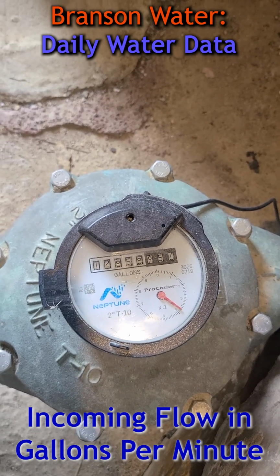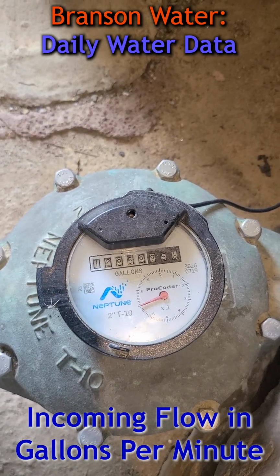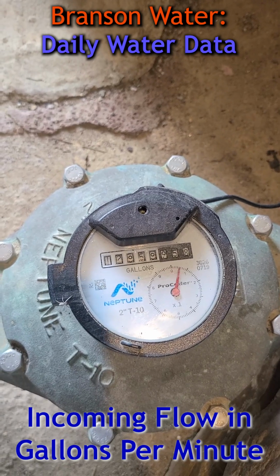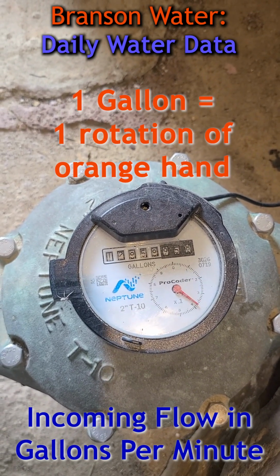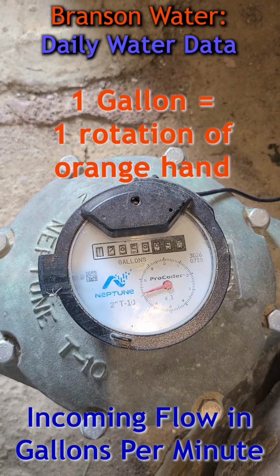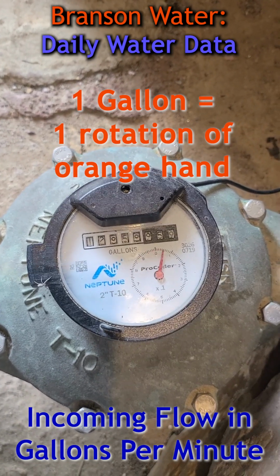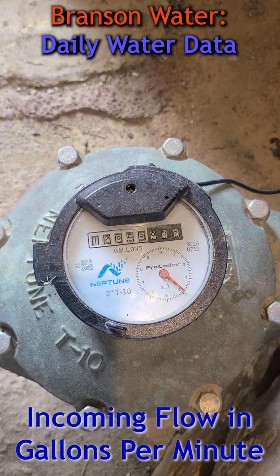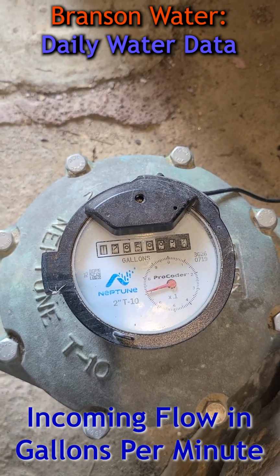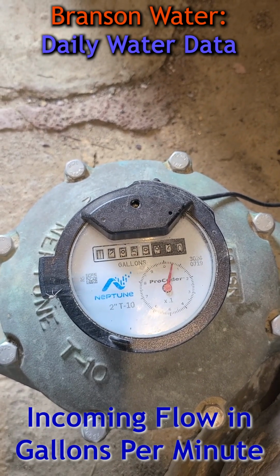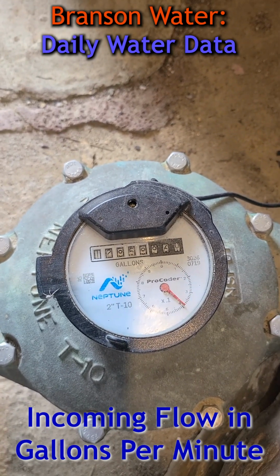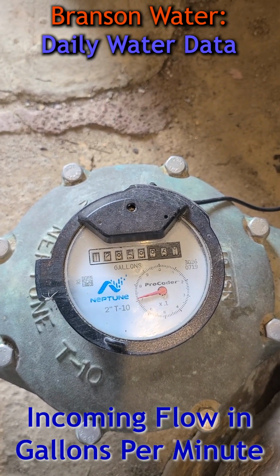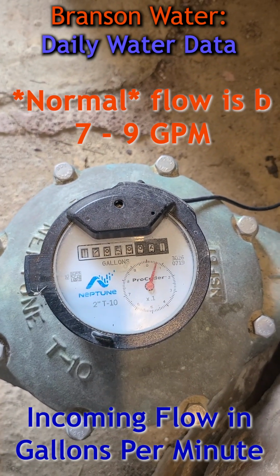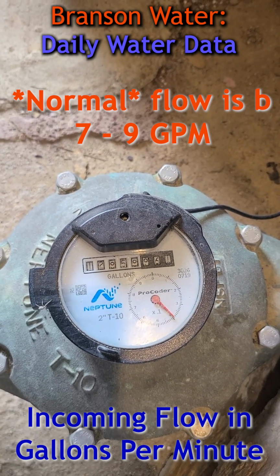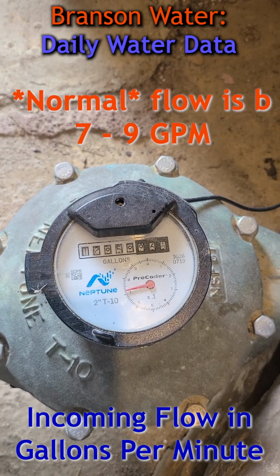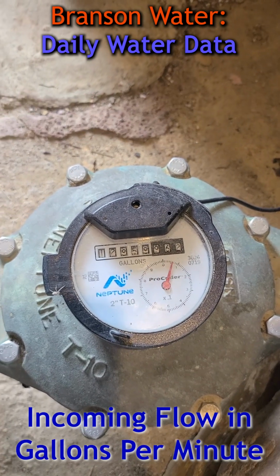The next thing you're going to do is calculate the gallons per minute. That is figured out by watching that orange dial go round and round for 1 minute and counting how many gallons. Each time around is 1 complete gallon. Now you can easily set your timer on your phone to 1 minute and just count them up, or if you don't want to take a full minute to do it, you can set your timer to 30 seconds and count how many gallons and multiply by 2. That total gallons per minute figure is what you will record on a daily basis. A normal number for us is anywhere from 7.5 to 9 gallons a minute, and that will fluctuate based on whatever the springs are doing.